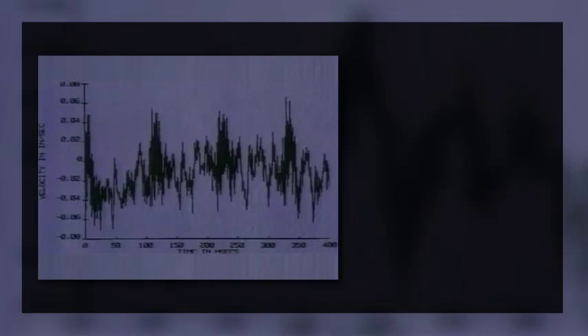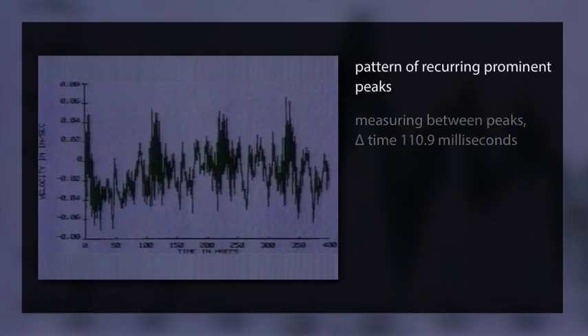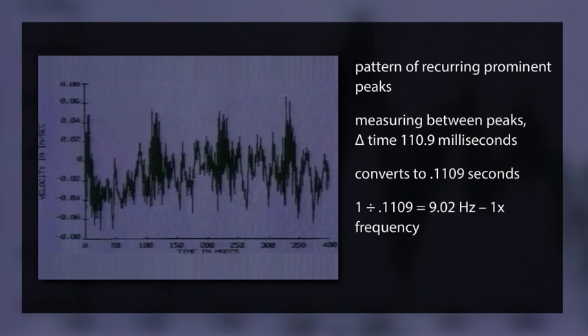Let's confirm our finding in the time domain. We find a pattern of recurring prominent peaks. Measuring between the peaks, we find a delta time of 110.9 milliseconds, which converts to 0.1109 seconds. Taking the reciprocal, 1 divided by 0.1109 equals 9.02 hertz rounded, which very nearly approximates the one-times frequency. The predominant vibration is the turning of the shaft, nothing else.